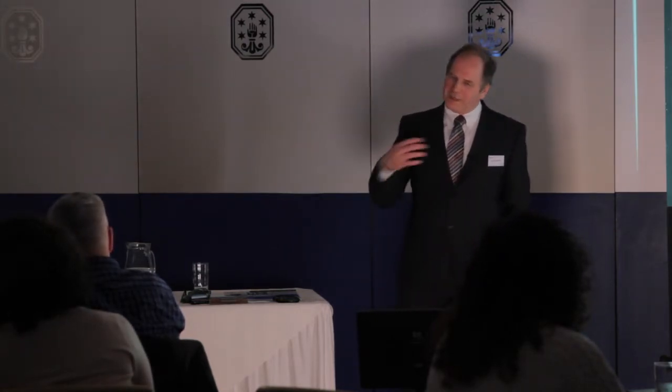But to actually pre-qualify a lot, I recommend you use it, because essentially we found that now we've applied this process, we don't have qualification challenges coming up because we're getting unexpected positives. We've had no problems before. It normally comes back, if you do an SEM analysis on those BIs that were used in that cycle, you'll see all sorts of problems. Have a look in the beginning, rule them out. But you have to have a setup to be able to do that.